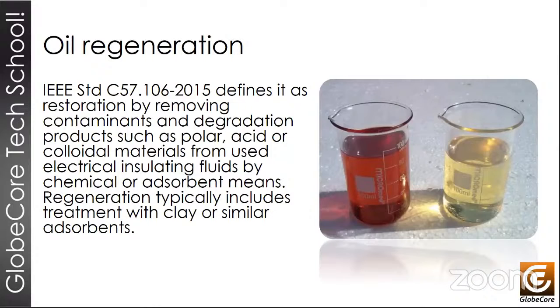A definition is that regeneration is a process that recovers oil. It removes contaminants resulting from decomposition, such as polar, acidic, or colloidal compounds, and usually employs adsorbents that allow us to regenerate the oil. In this picture, you can see an example of oil before and after regeneration. You can obviously see the improvement in color, which is also a very important indication of quality, as you'll see in the next slide. Next slide, please.